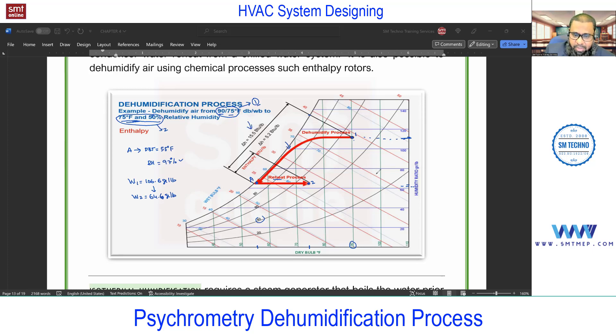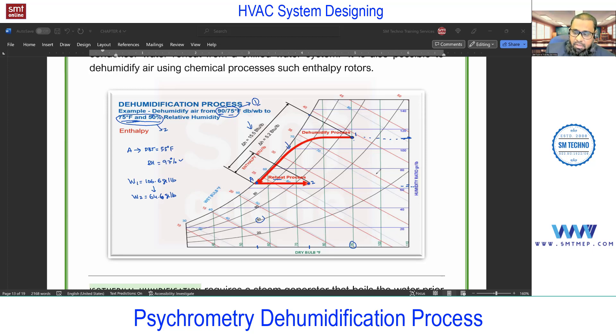Compared to the cooling coil, the capacity of the reheat coil is very small. The heating coil can be a separate electrical heater (resistance heater) or it can be waste heat energy from the condenser or from the building. Adding sensible heat from A to 2: you can see the dry bulb temperature increases by adding heat only — the humidity ratio stays constant.